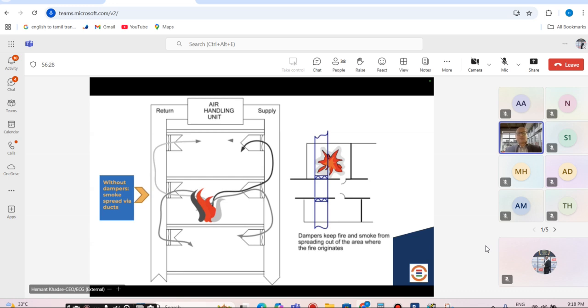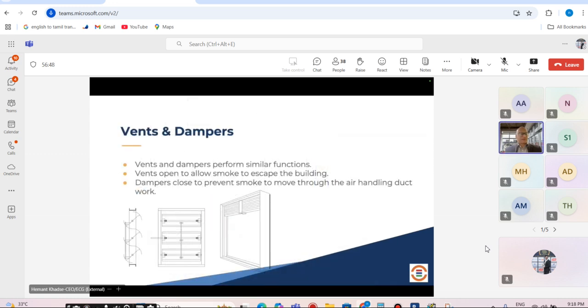Are you building more than one floor adjoining as the pressurized smoke zone, or you have only the exhaust opening on that fire zone? So this is again part of your engineering, how your dampers are going to be acting as the barrier to restrict your smoke from going horizontally or vertically. Vents and dampers are interchangeably used, but vents are basically intended to open so smoke can escape the building, that is negative, and dampers are basically to close the airflow or the smoke flow. So that's how it is part of your design.